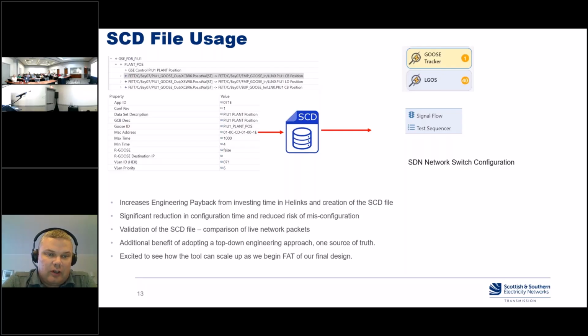Validation of the SCD file, like I said, comparison of live network packets is another really good aspect of it. It gives you confidence that what is in your device is what is in the file and is what is on the network. So you have that validation that everything's configured well. And the additional benefit is having the one source of truth from the SCD file.